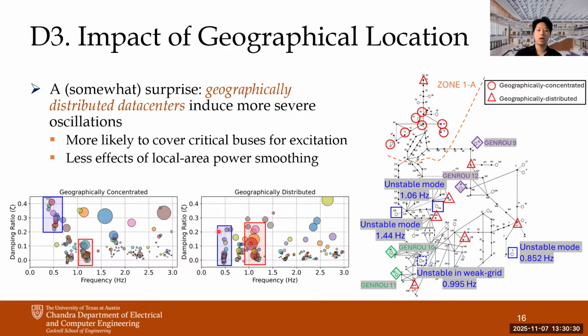As you can see from this preliminary analysis, there's a larger oscillation in the distributed cases, and we think this is because of the power smoothing effect in the concentrated cases. And in this lower frequency zone, although there are similar magnitudes of oscillation around 0.5 hertz, you can see a much lower damping ratio in the distributed cases. So this should arise from the first factor, which means that distributed data centers may excite the lower frequency mode around 0.5 hertz in the WECC system.